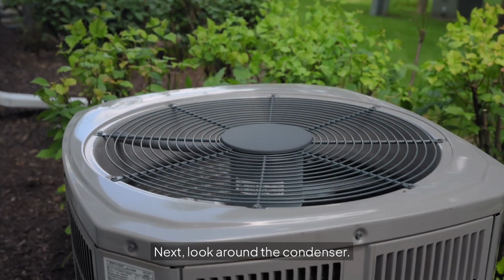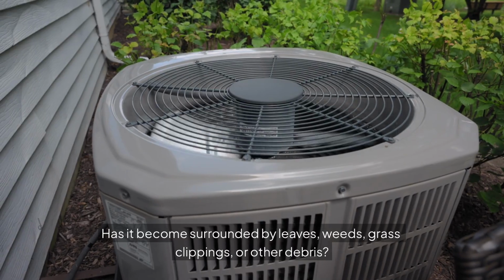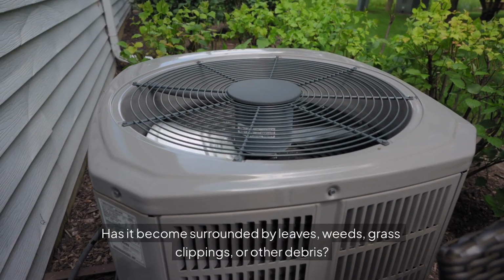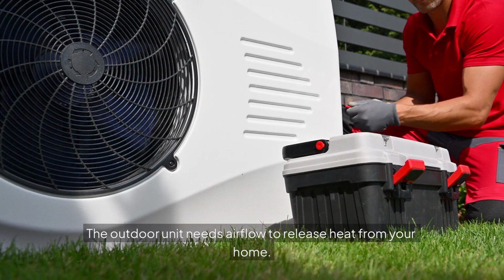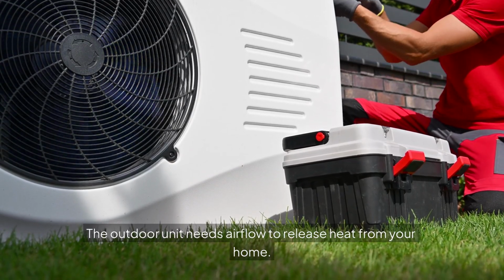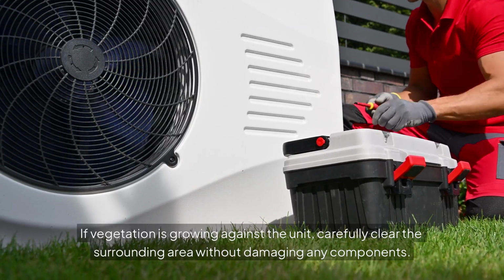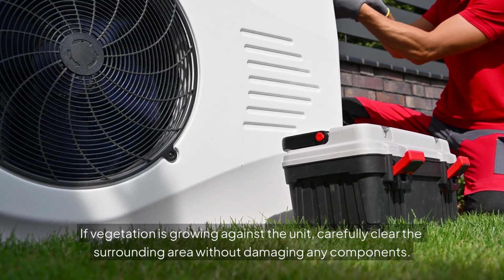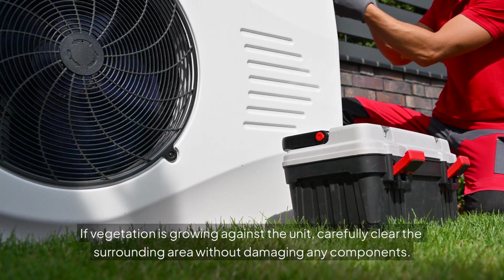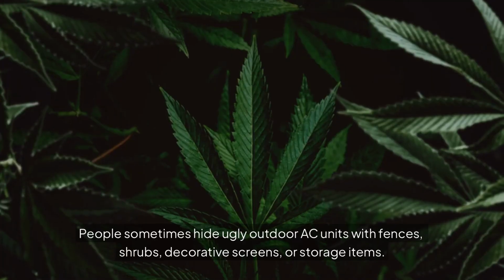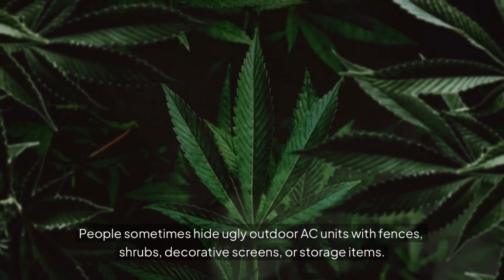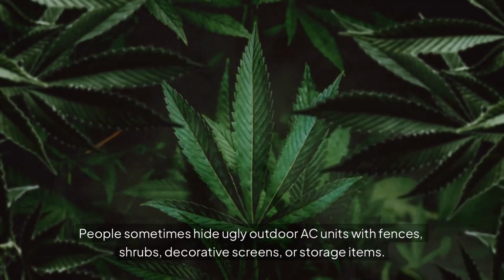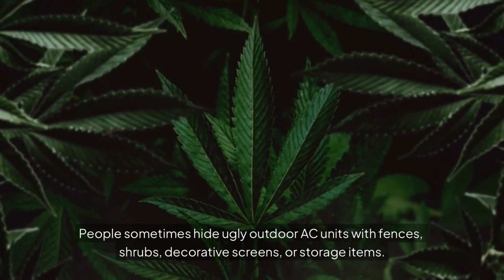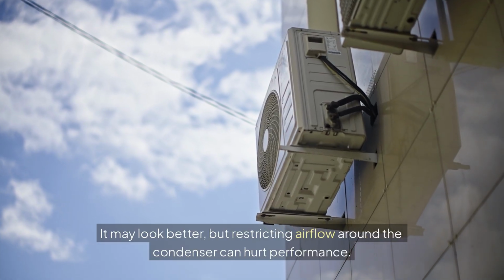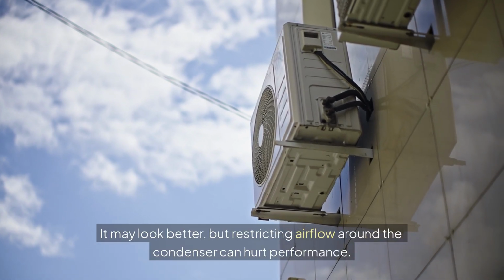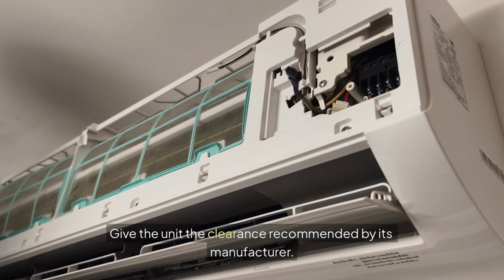Next, look around the condenser. Has it become surrounded by leaves, weeds, grass clippings, or other debris? The outdoor unit needs airflow to release heat from your home. If vegetation is growing against the unit, carefully clear the surrounding area without damaging any components. And here's a common mistake. People sometimes hide ugly outdoor AC units with fences, shrubs, decorative screens, or storage items. It may look better, but restricting airflow around the condenser can hurt performance. Give the unit the clearance recommended by its manufacturer.